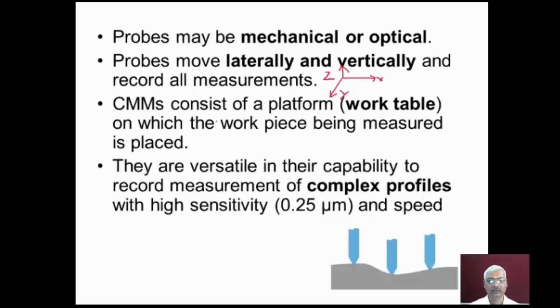Coordinate measuring machines consist of a platform, that is a work table, on which the workpiece being measured is placed. Depending upon the requirement, a fixture may be used to mount the workpiece, or the workpiece can be directly placed on the work table for measurement without using any fixture if it is a simple workpiece. They are versatile in their capability to record measurements of very complex profiles with high sensitivity and speed. Whenever we need to measure complex profiles, we can use a scanning type of mechanical probe which will move along the surface, and then data points are recorded, and the profile can be evaluated.